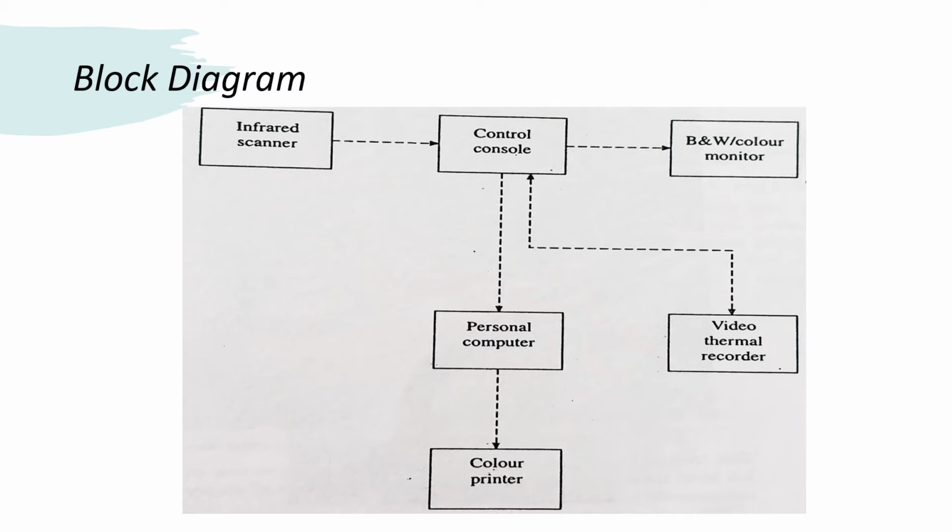The block diagram of a non-contact thermography system is shown in this figure. It basically consists of an infrared scanner, monitor, control unit, and a calculator for field application.